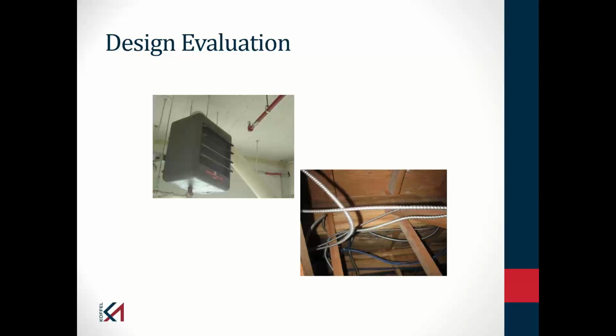heat-producing equipment. I mean, I was involved in a litigation case where a yoga studio, which had sprinklers in it, was converted to a Bikram yoga studio. And the sprinkler was too close to that unit heater, and the sprinkler activated, causing a fair amount of water damage. But 25 is going to put that responsibility on the owner or the owner's representative. If you hire a contractor to do the inspection, test, and maintenance on your system, they most likely are not doing that. And whenever I am involved in a litigation case where there are design or installation problems with the system, the typical defense of the contractor providing the ITM services is, that's outside our scope. Look at Chapter 1, NFPA 25, says we don't have to verify the design and the installation.